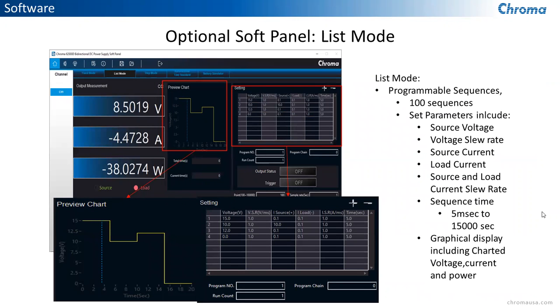In addition to being able to do a fixed mode, we also have programmable sequences. We refer to that as list mode operation. We can do up to 100 sequences. Each sequence can have a time from 5 milliseconds all the way up to 15,000 seconds. And you can do that with voltage and current settings as your source, and with current and load settings for operating as a load. You also have the ability to set the slew rate for the device, rising and falling edge, when it's transitioning from one sequence to the other.